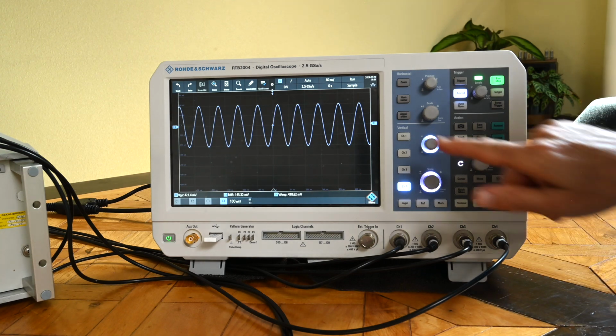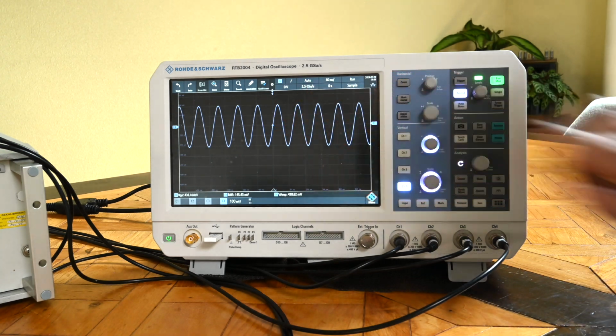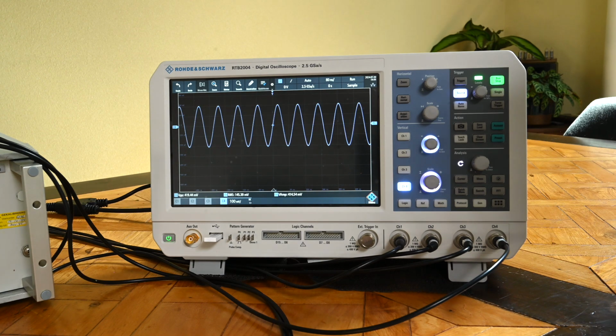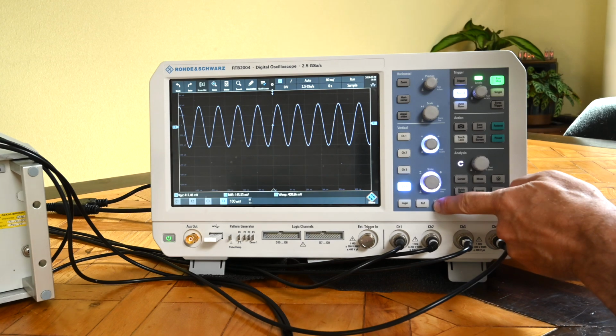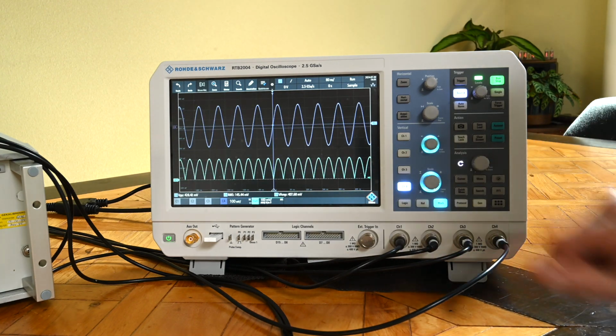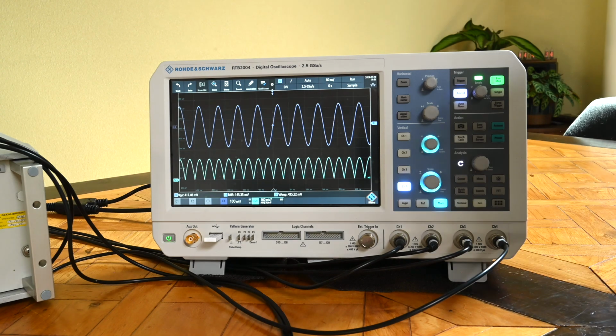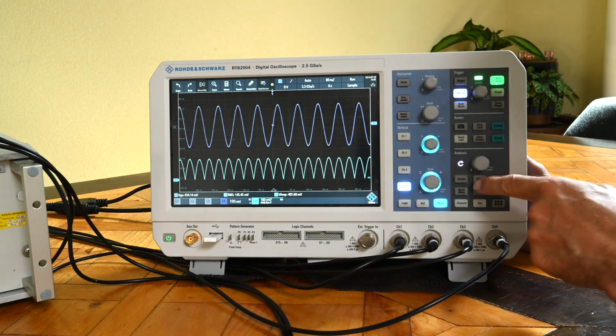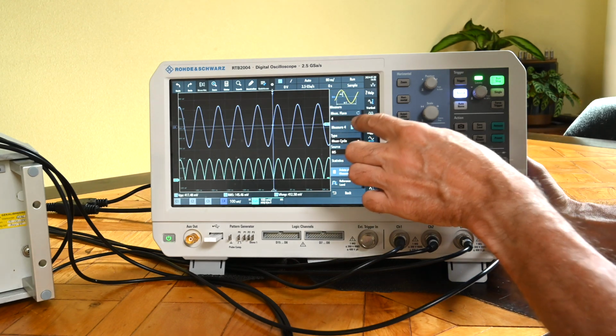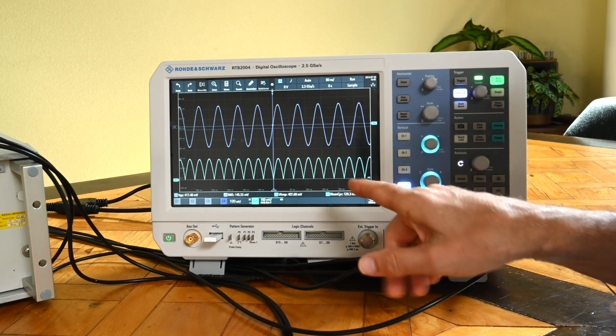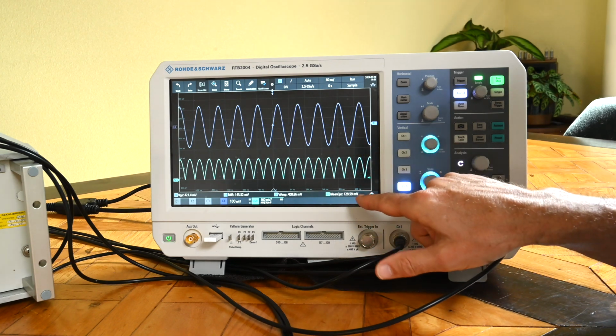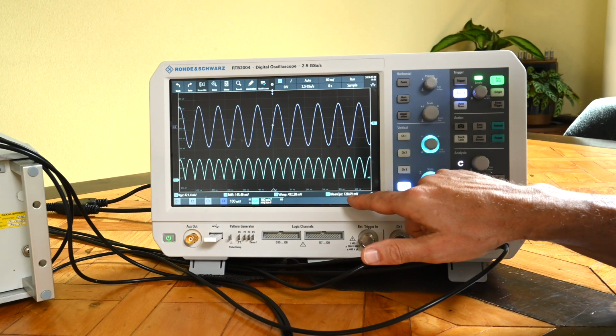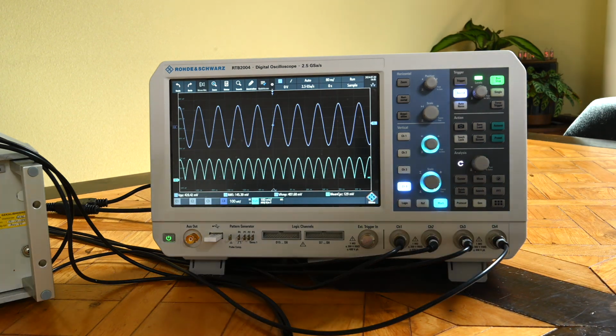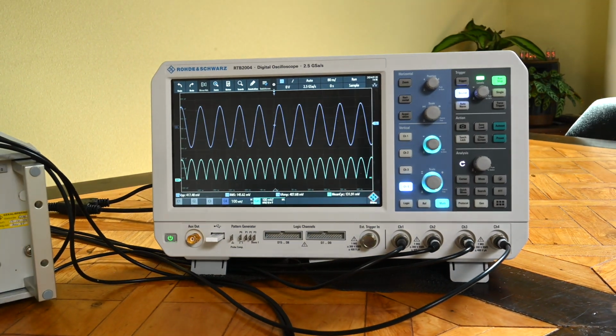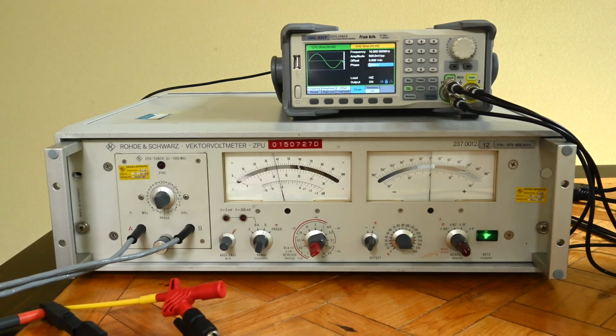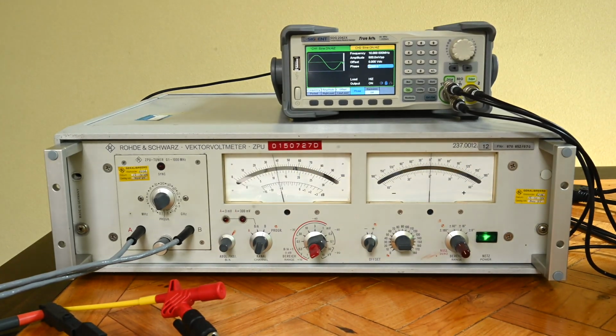I think the voltmeter is just looking at the positive part only, the upper part of the sine waves, and taking that average. To see what that value is, we can create that signal here with the math function. I already created it here. This is just the absolute value. I also created a measurement value that can show us what it is. So I'm activating measurement number 4. There we go. We're seeing that out of this absolute signal, the mean value is 120. And I think that could be pretty much what we're actually reading on the device itself. That's the voltage level that the device is reading.